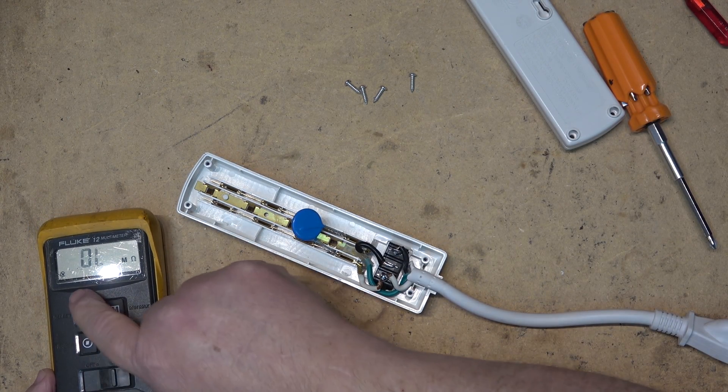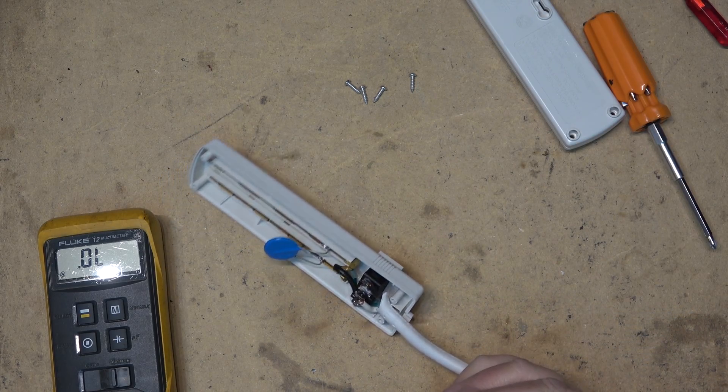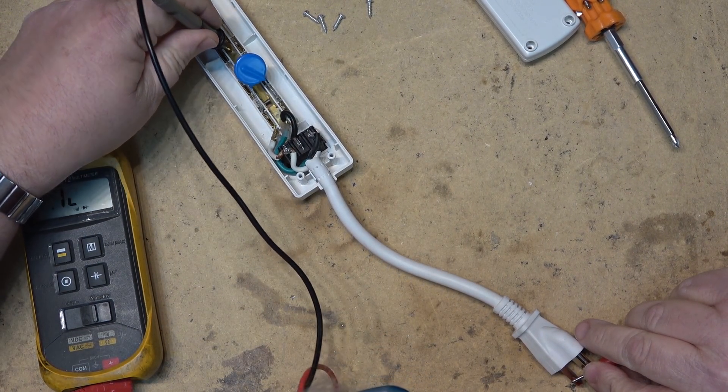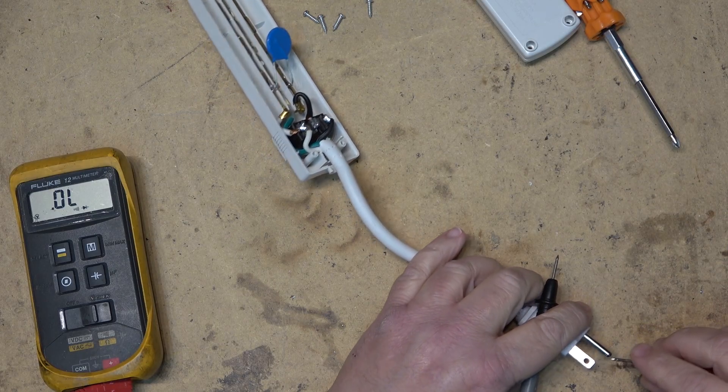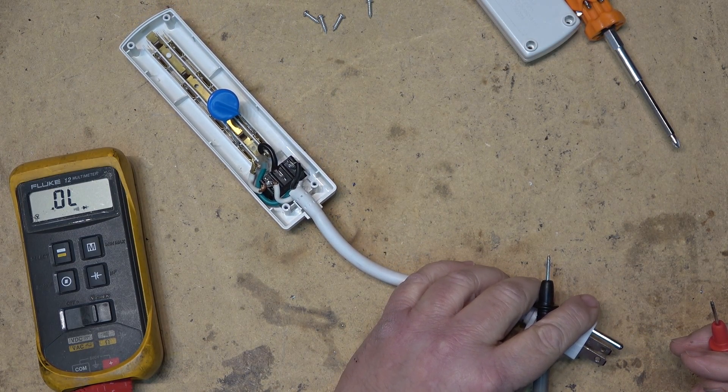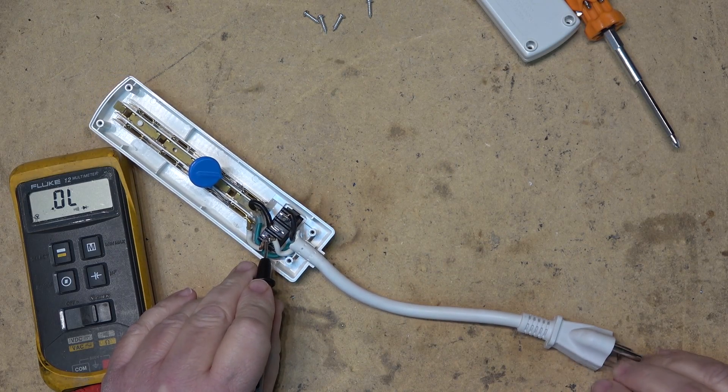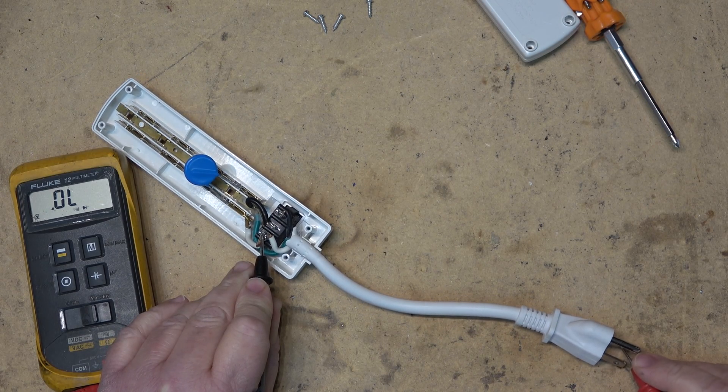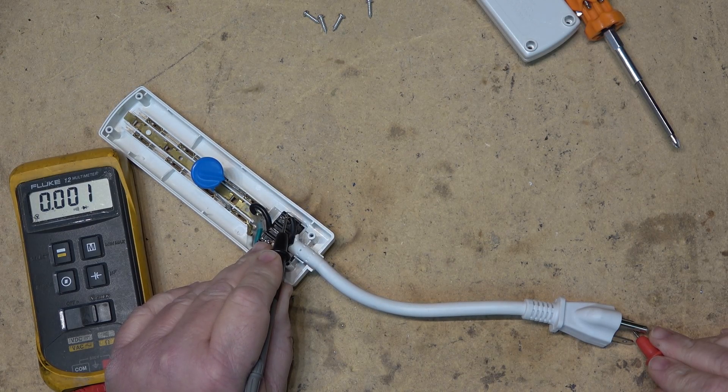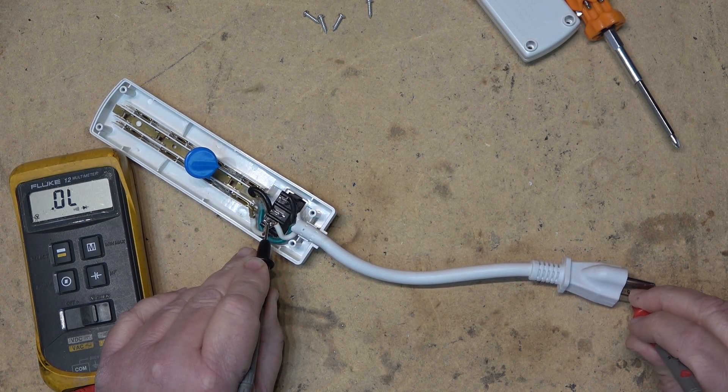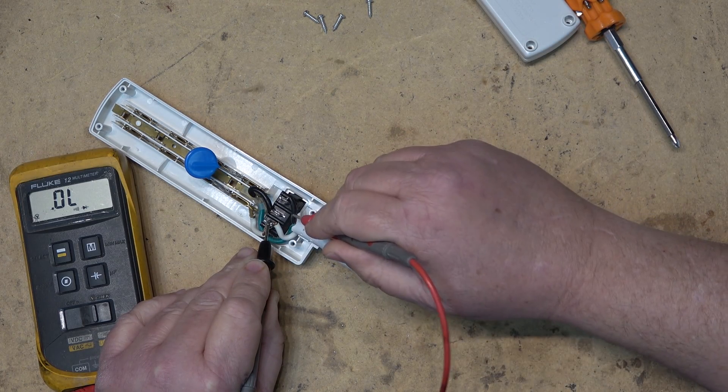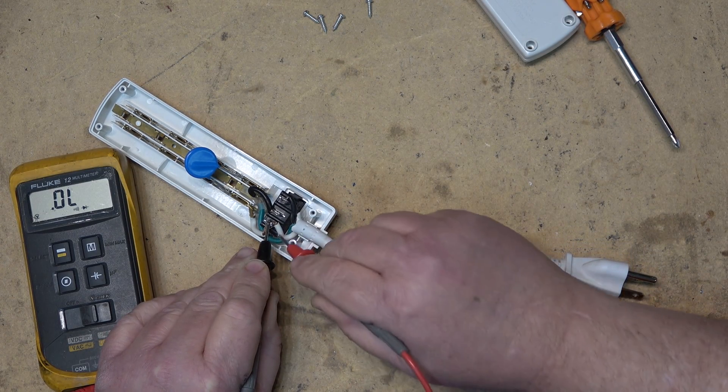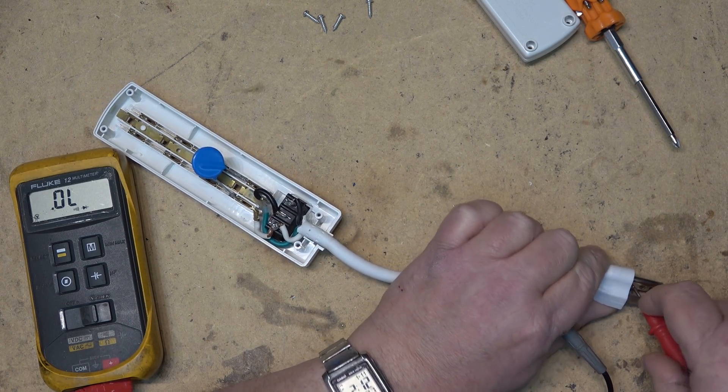Ohms. I'll put it in diode test so it beeps. We'll see which one of these went open. So we'll first measure the ground electrode. I don't expect there'll be an open there. Okay, now which one's which? Let's see here. This should be the neutral. Neutral is open, interesting. Both these sides are measuring open. This should be the hot one here and hot works, hot works and the neutral went open. Isn't that interesting? I was fully expecting that switch to be the fault and what's happened is the line cord here has gone open between neutral and here, somewhere between here and the prong.